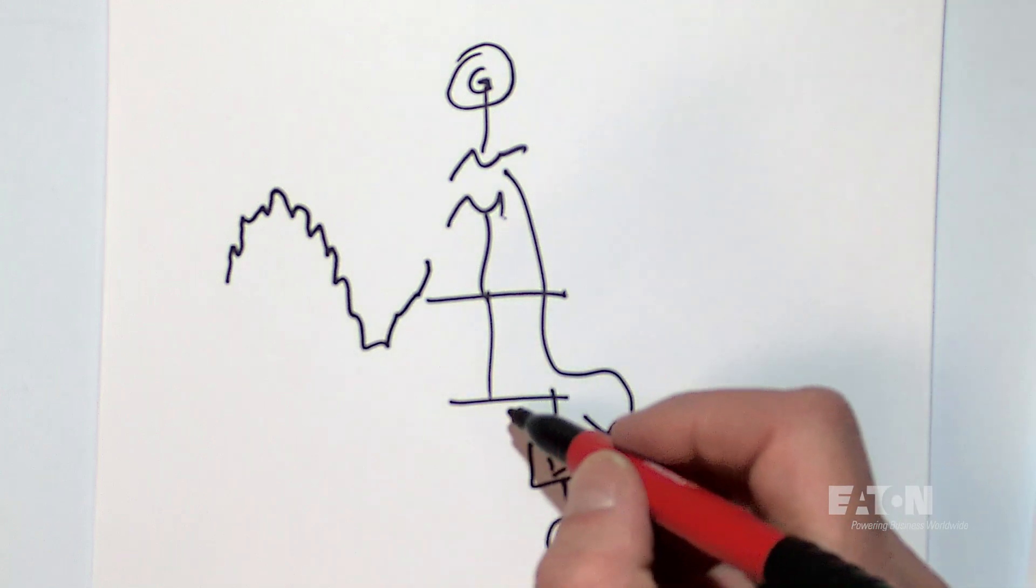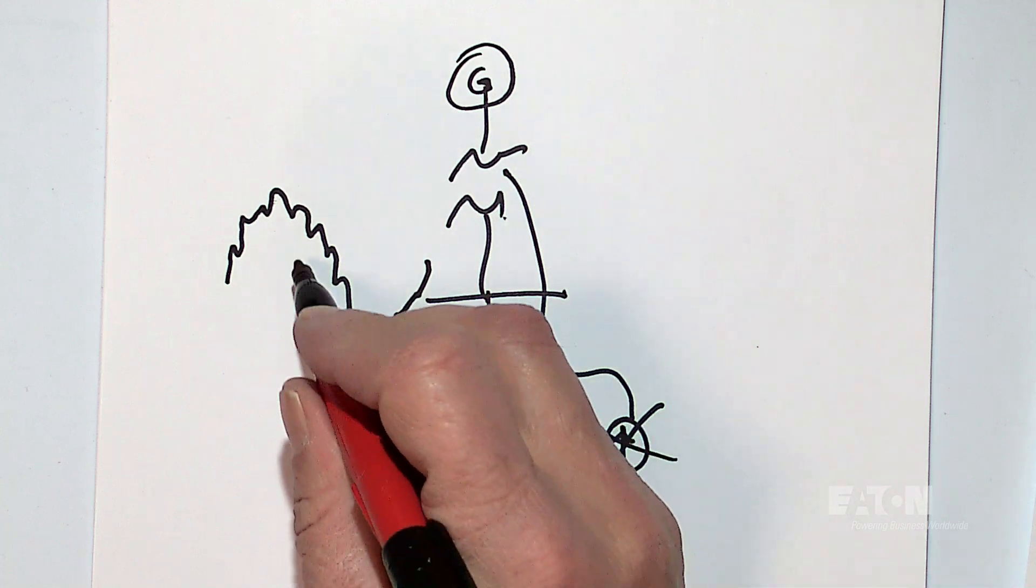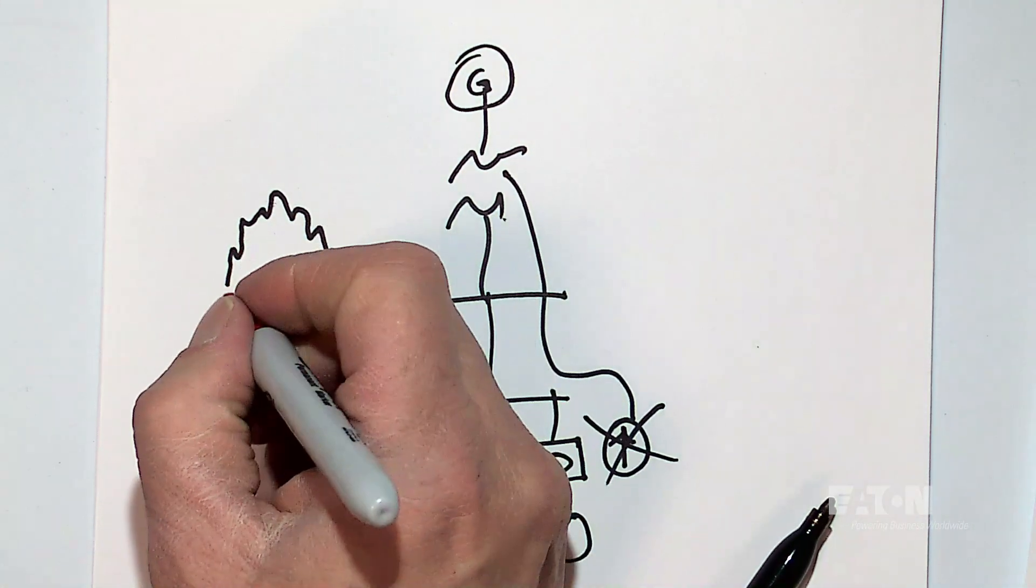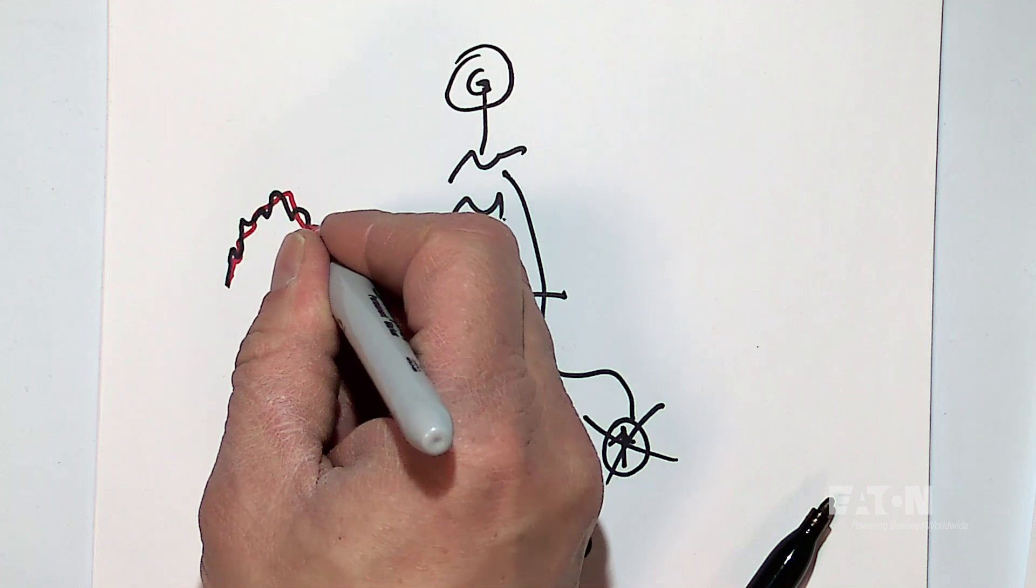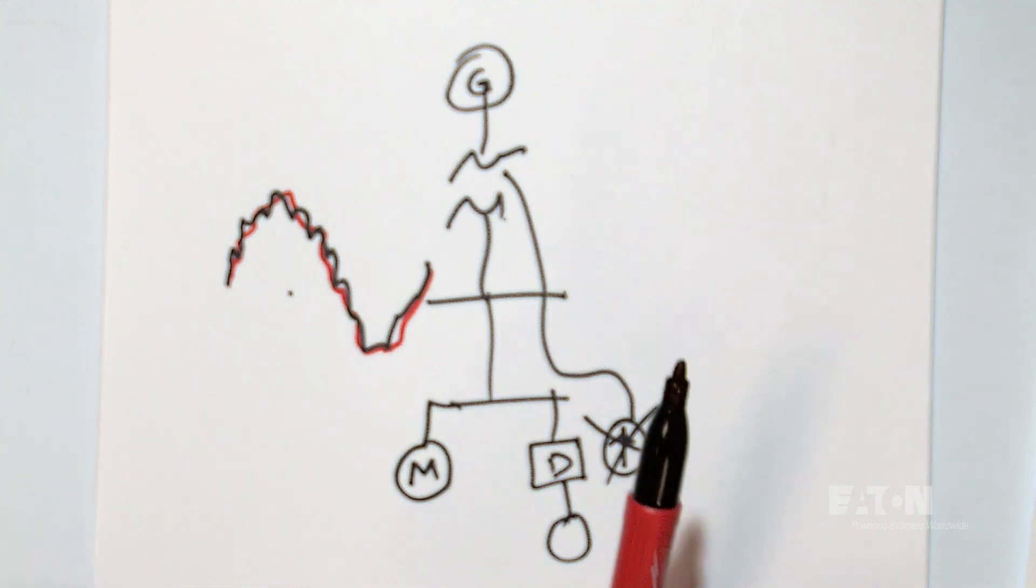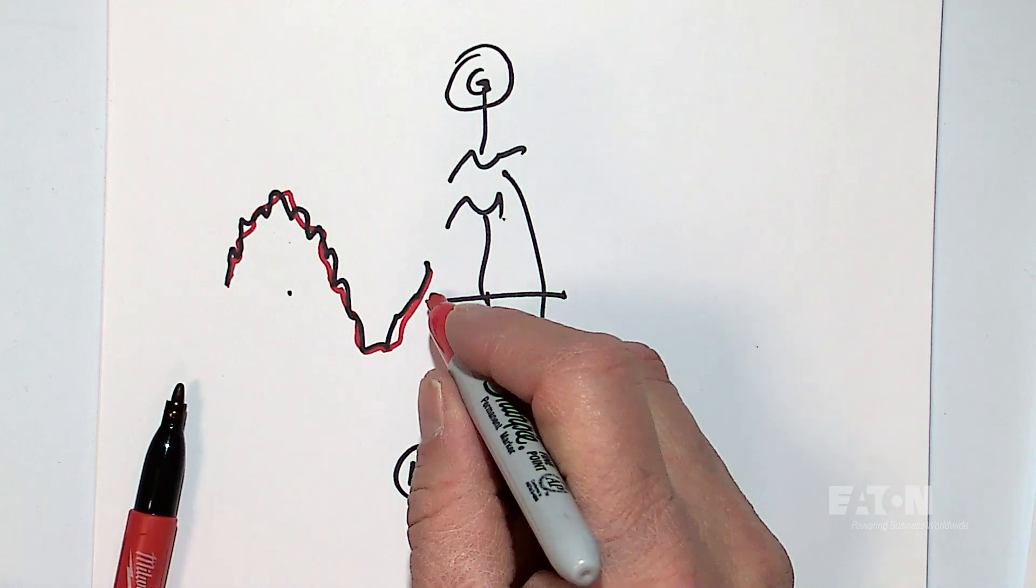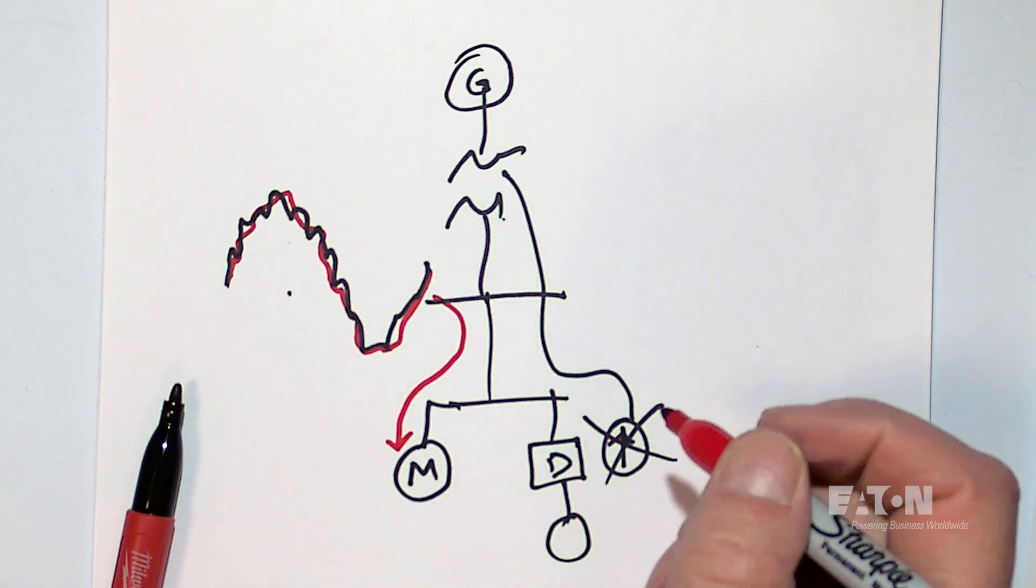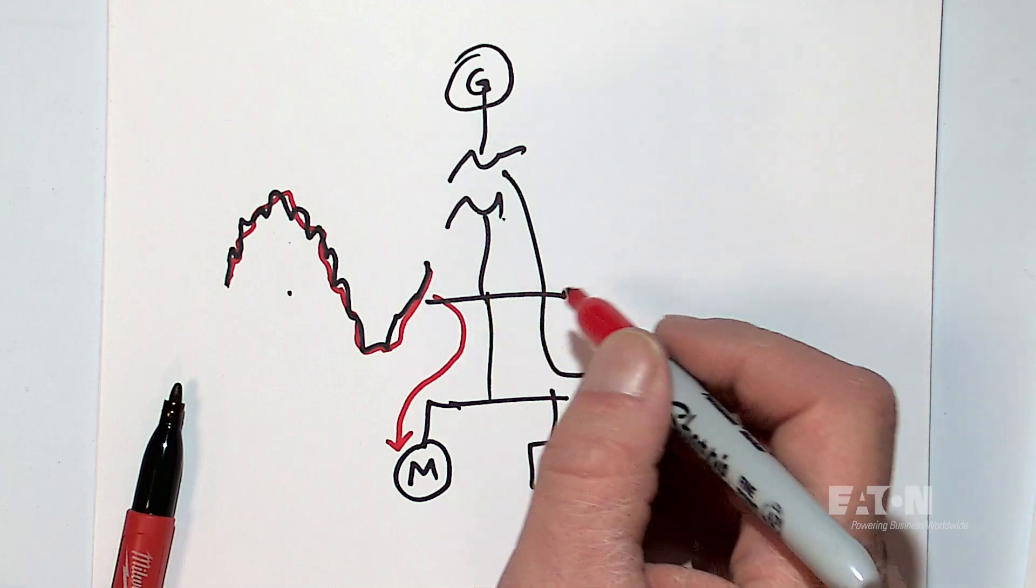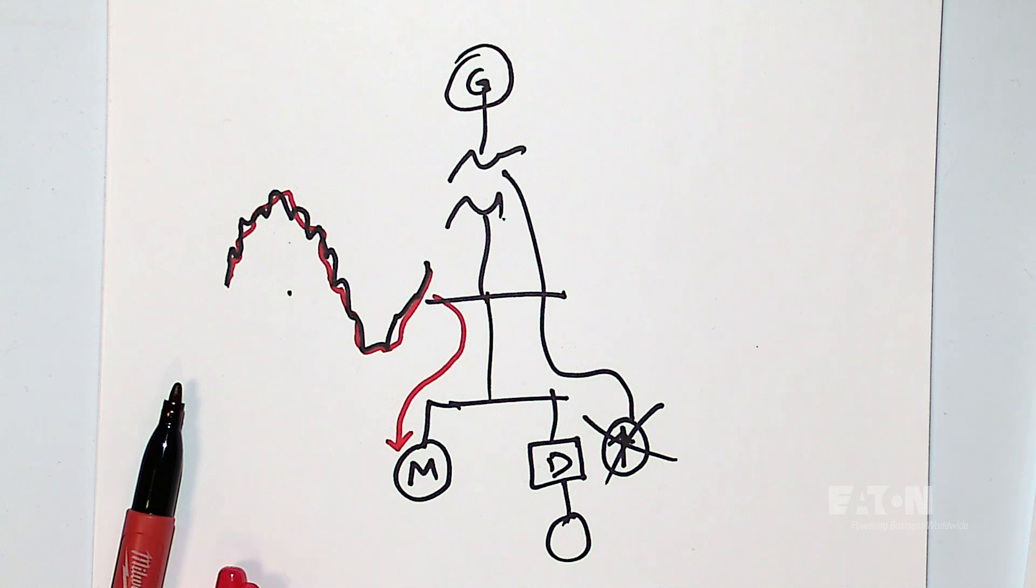We're going to draw a current down through, for example, a motor that's across the line that's proportional to that voltage. So the current would in fact maybe look—and it could be out of phase—but it could look distorted. So in fact, you have voltage distortion causing the current distortion, but it's a more unusual situation this way. Current would flow this way toward the load from the source that's distorted. But ultimately, the reason that the voltage source is distorted is because of harmonics somewhere in the system, unless that generator itself is creating harmonics on its own.